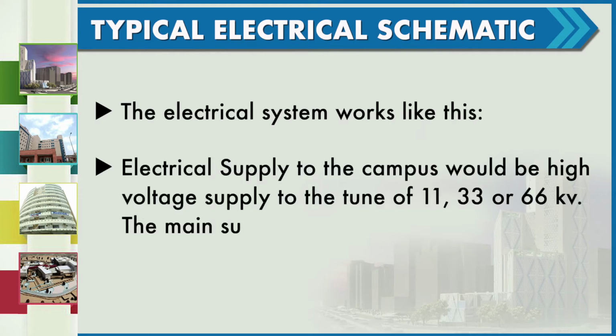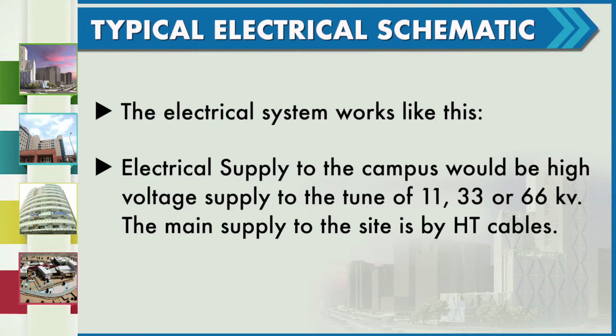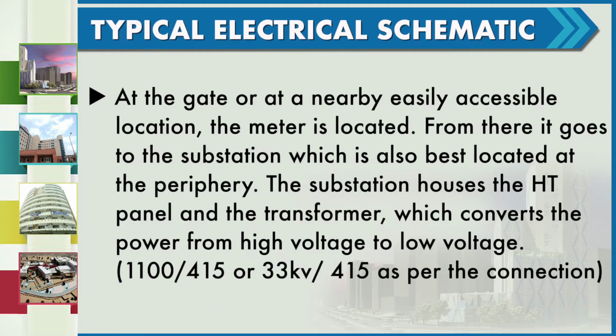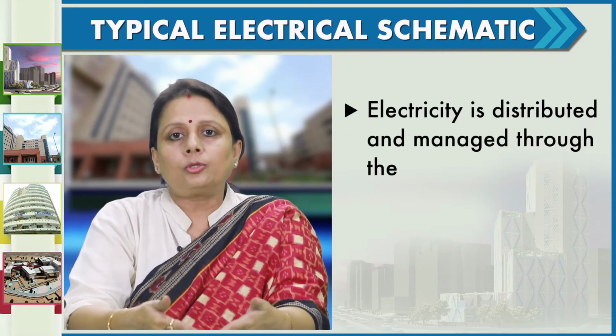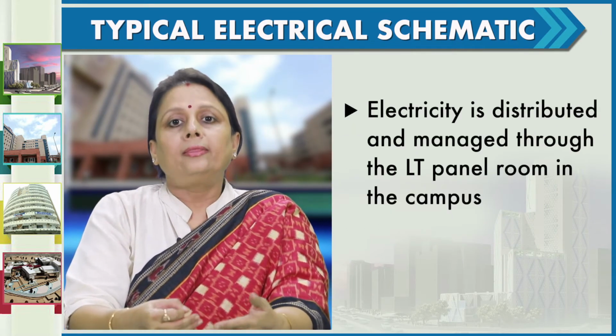Electrical supply to the campus would be in high voltage supply to the tune of 11, 33 or 66 kV. The main supply to the site is by HT cables. At the gate or at a nearby easily accessible location, the meter is located. From there, it goes to the substation, which is also best located at the periphery. The substation houses the HT panel and the transformer, which converts the power from high voltage to low voltage that can be used, for example 11 kV by 415 V or 33 kV by 415 V as per the connection. Electricity is distributed and managed through the LT panel room in the campus.